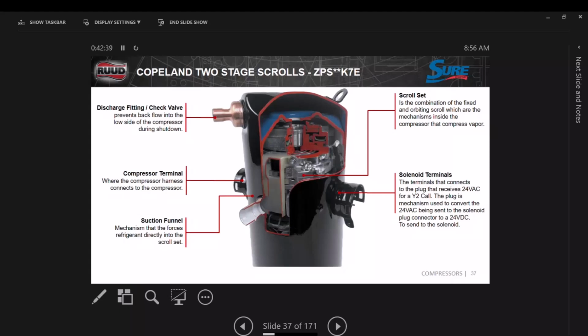Because you can warp that valve in there. It's a plastic valve. Okay, so if you're changing out a compressor, always remember to protect that thing. And if it warps, then the compressor is gonna sing to you when it shuts down. We have our compressor terminal plug over here. That's the plug that plugs in for high voltage. We have our solenoid terminal that plugs in here, another plug that plugs in. This is our rectifier plug.